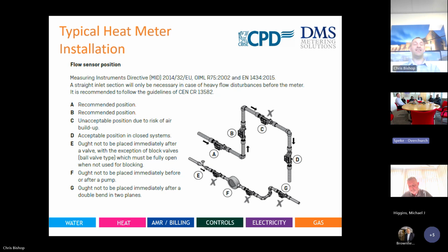So what you're doing is designing the meter to be installed on the return to keep the heat meter body away from other devices, and that's generally the pumps. Pumps can affect the accuracy of flow meters. Even flow meters next to pumps can affect the actual performance of a pump. So it's getting that balance right between the pump installation parameters and the heat meter installation parameters. Some get it right, some get it completely wrong.